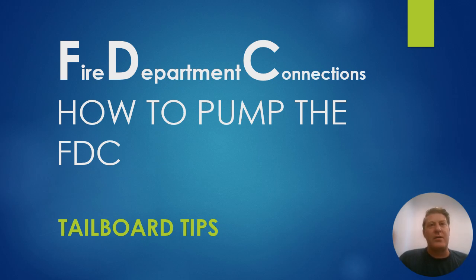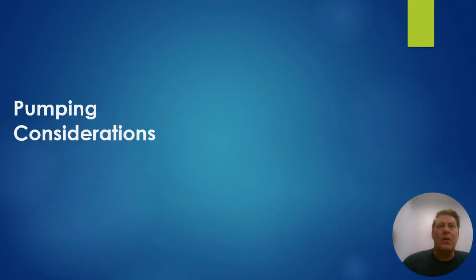All right, video 3 and the last of our three-part series in Fire Department Connections, how to pump the FDC. All right, next we're going to talk about some pump considerations. Number one, once we've got everything connected, we know that we're hooked up to the right standpipe or sprinkler system. We've got to charge the lines and then throttle to a pressure. We'll typically set our pump discharge pressure at 150 psi.